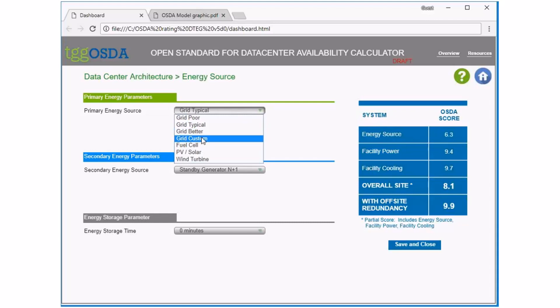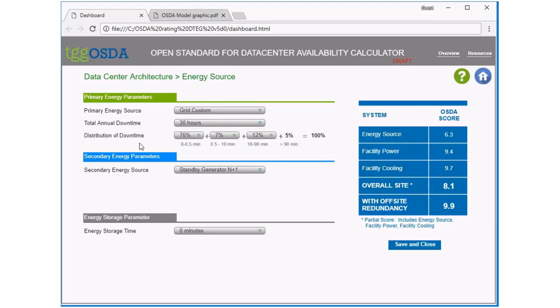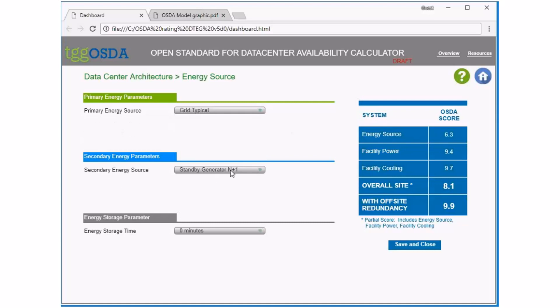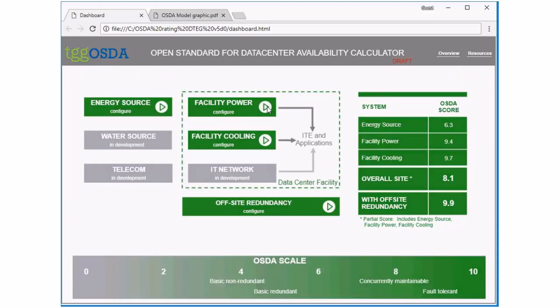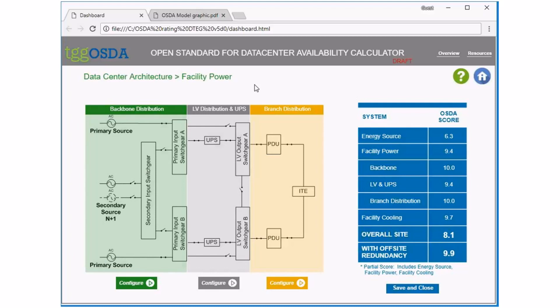Under energy source you can see we have a primary, a secondary, and also energy storage. We've loaded a typical scenario of grid-typical with a standby generator. Clicking on the grid, you can see different options from the grid to fuel cells and wind turbines, etc. Under grid custom you can actually customize your probability distribution function — you can pick the number of annual statistical hours of outage and distribute where those outages occur in duration. I'll change this back to typical. With secondary energy source as a standby generator, we also have a fuel cell and different configurations of generator, giving us an energy source score currently of 6.3.